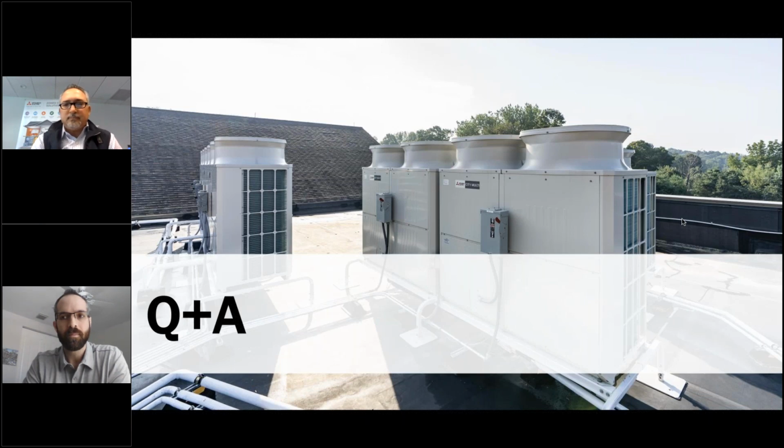Right, excellent. Next question. What is the typical lifespan of a VRF system, and how does that impact tax strategies? So I'll answer the first part, and I think George will take over the second part. The typical lifespan of a VRF system is rated by AHRI, I think at 15 years. We've got systems that have been running for 25 years plus in commercial applications in the US. The inverter compressor really is a soft start, so you don't get that big spike in energy that dims the lights in your house or resident room when something kicks on across the line.